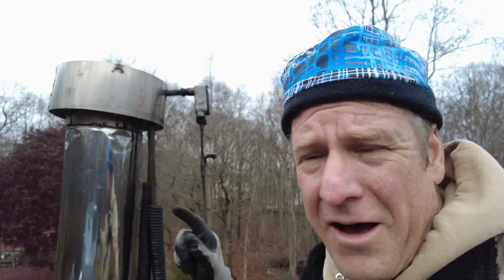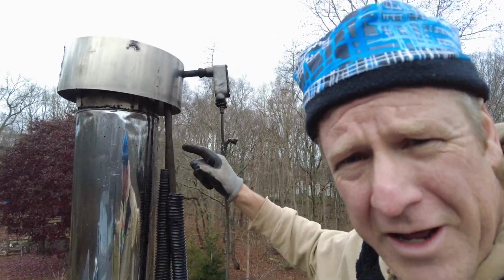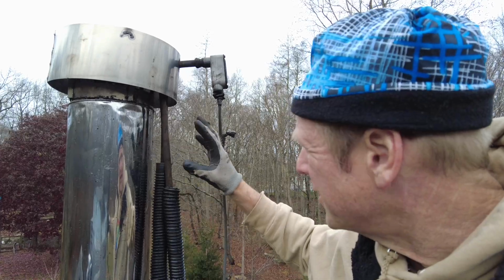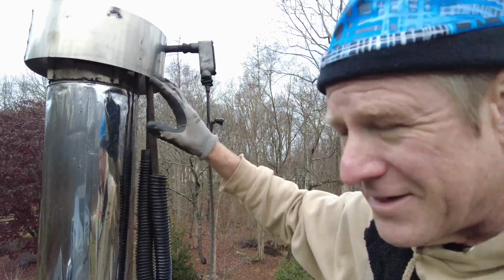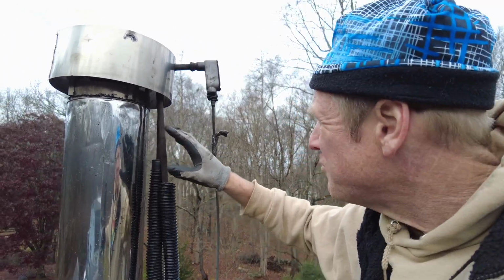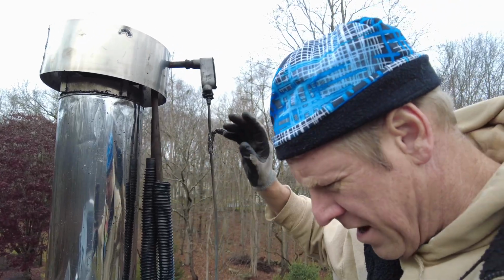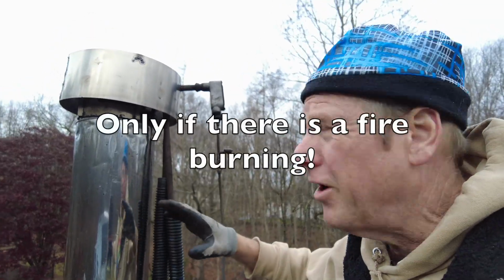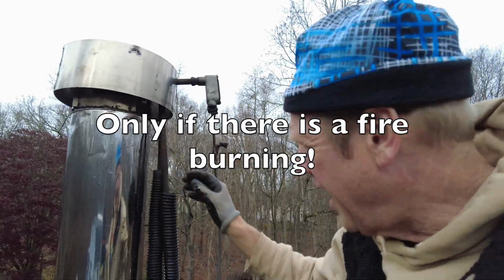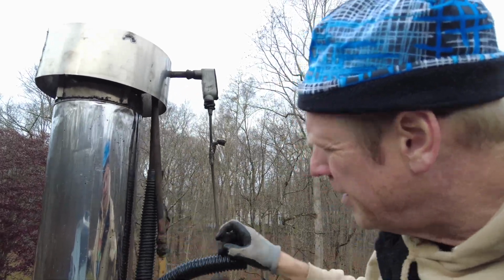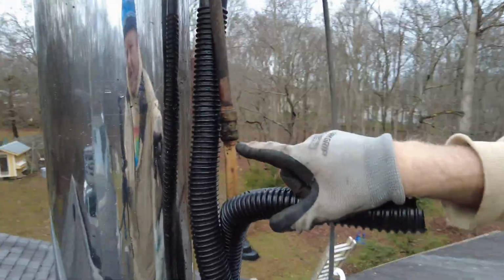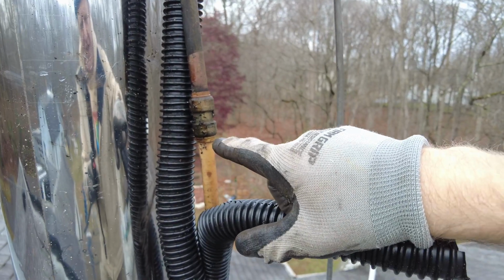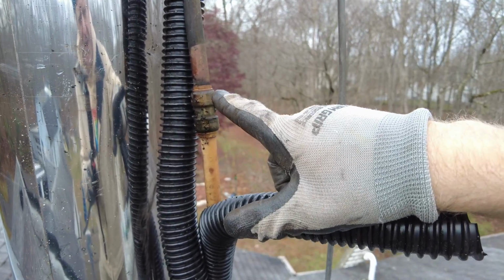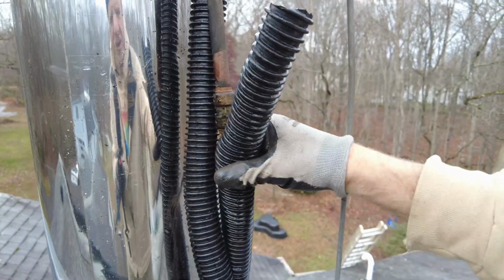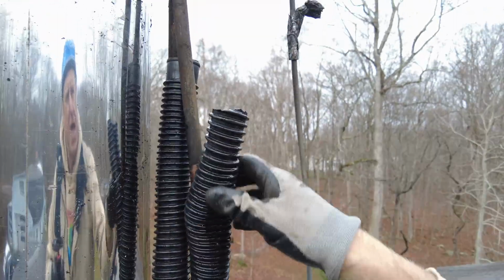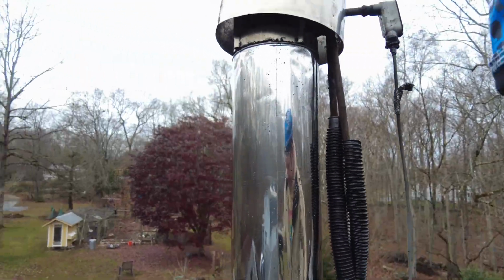So that sits up on the top. Now I need to go down and make sure that the fluid, the antifreeze fluid, is circulating through this, because if it's not circulating for any reason - bad switch, plugged line, faulty pump, whatever - this thing will collect heat and then it will pop off this PEX right here, because the PEX will heat up and then the pressure will pop that off.